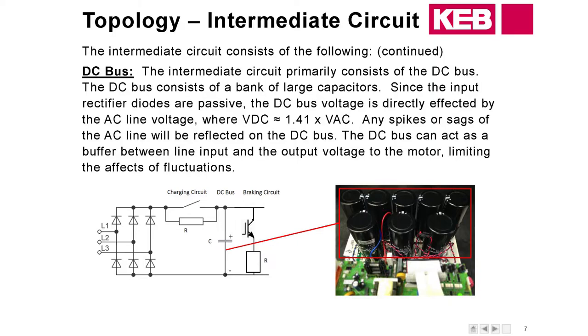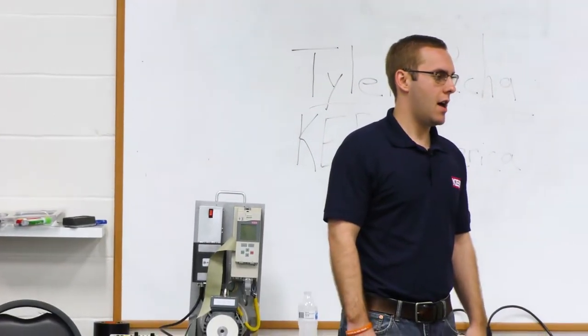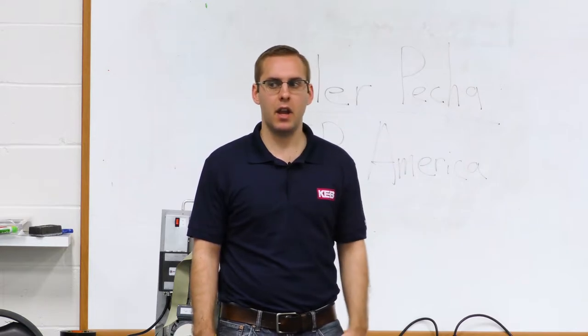As far as the DC bus goes, it's going to have your bank of capacitors, which will look slightly different depending upon your housing size but are pretty easily identifiable by the black caps. A good way to figure out where your DC bus should be sitting is to measure your AC voltage phase to phase on the incoming and then multiply that by 1.41 — that gives you an approximate DC bus value. The DC bus will smooth out some line fluctuations, however if the fluctuations — whether a sag or a spike — are severe enough, that will be reflected in the bus as well.